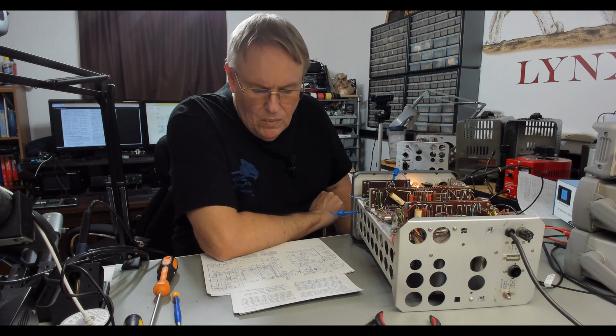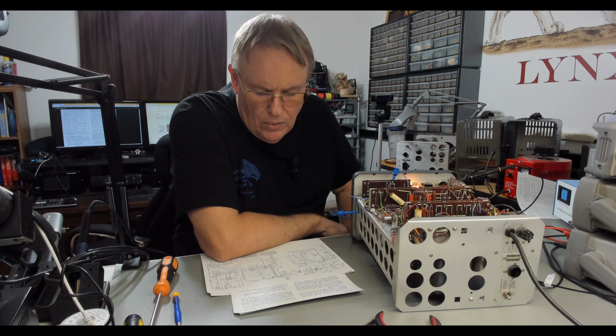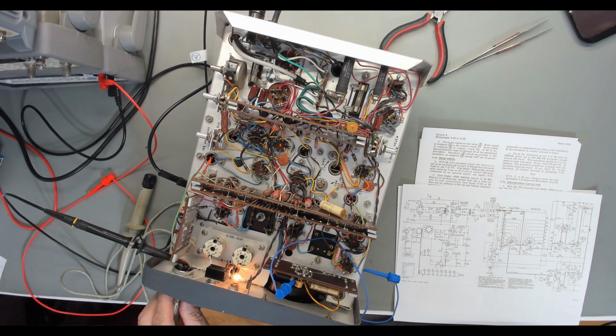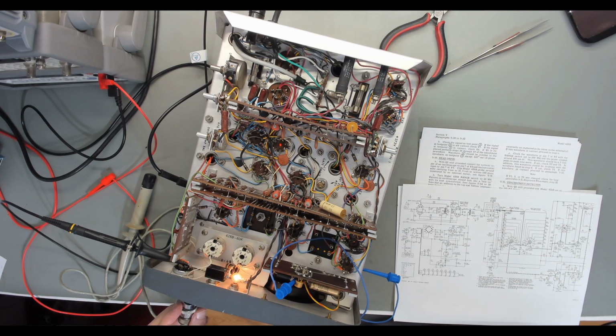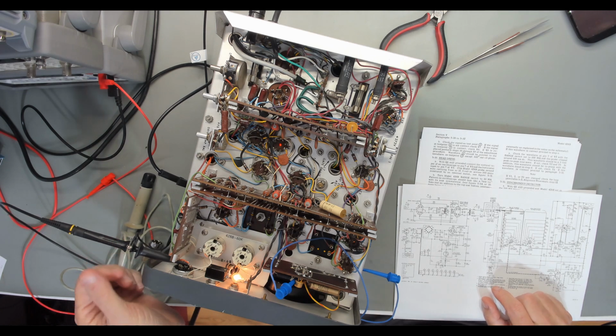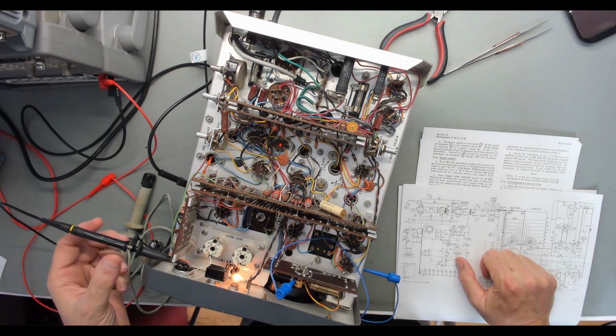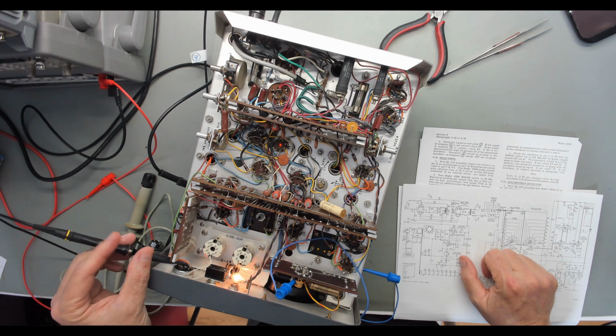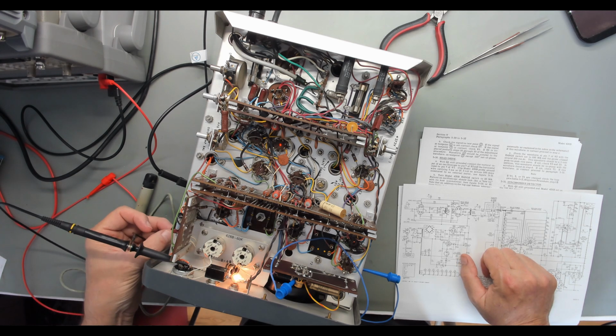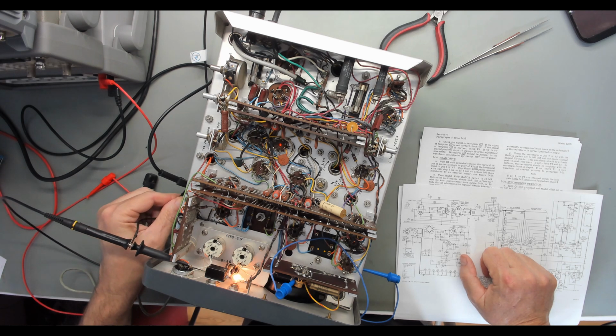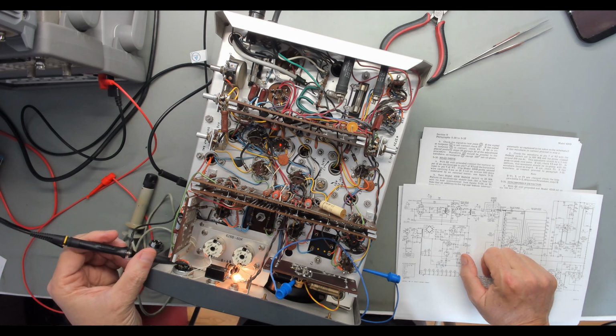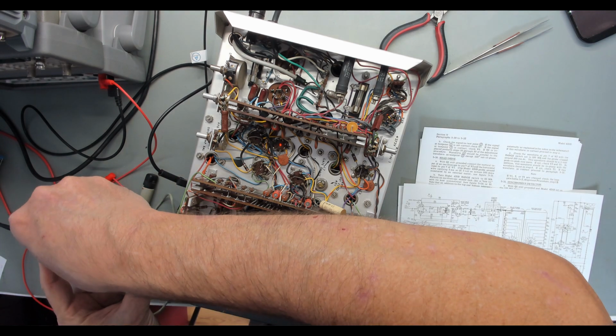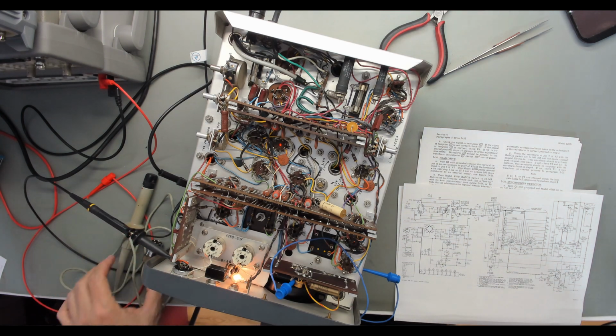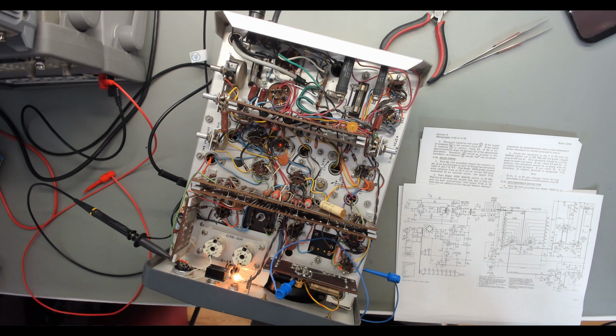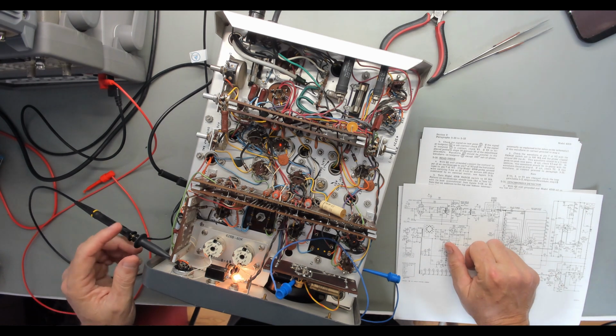Because why would one side of a transformer be one thing and the other be another? It's interesting, without the probe you get no signal. Well, you get a little signal. Get kind of more of a sine wave. What do I get on this other one? You have a good ground, right? Here, let me do this. I know I'm getting a good ground there. Let me move this from here carefully because I'm still powered up. Yeah, no, it ain't going to be the probe because the probe's disconnected. Probe disconnected, I'm getting the same voltage, but I'm getting a lot less voltage here.